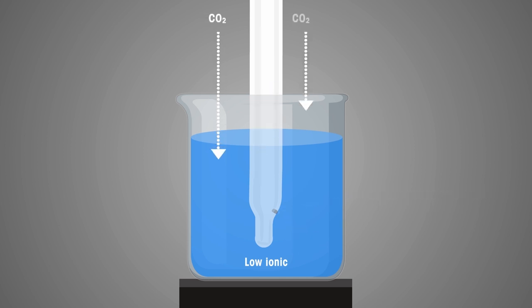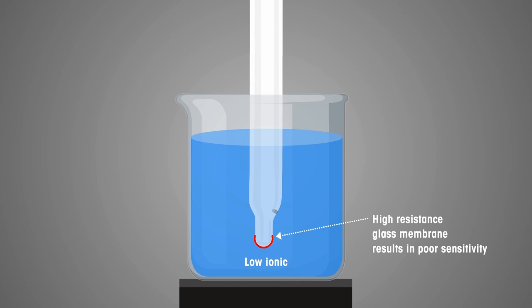Further, the low ionic concentration makes pure water susceptible to ingress of carbon dioxide from air. This absorbed atmospheric carbon dioxide becomes carbonic acid in the sample. Therefore, the pH value changes, and wrong results may be obtained. Inaccurate results can also occur due to the lack of sensitivity of the high-resistance glass membrane for hydrogen ions in low ionic samples. Thus, the pH value gets recorded without reaching an equilibrium, and therefore, the pH measurement accuracy gets compromised.